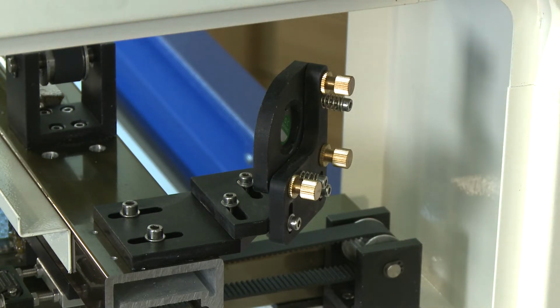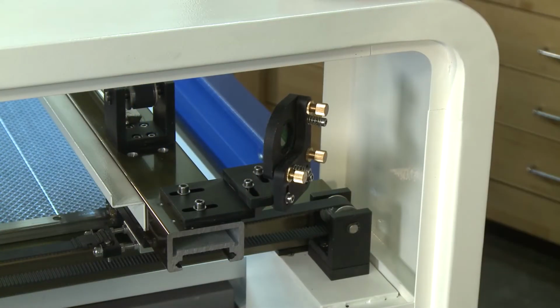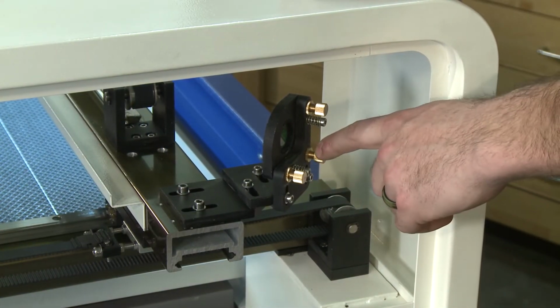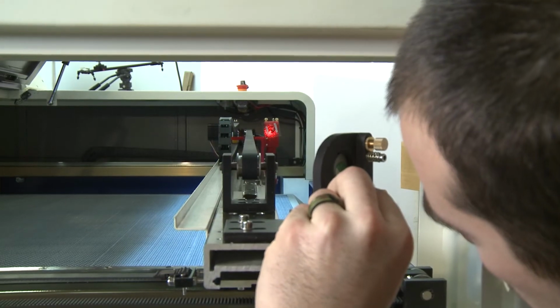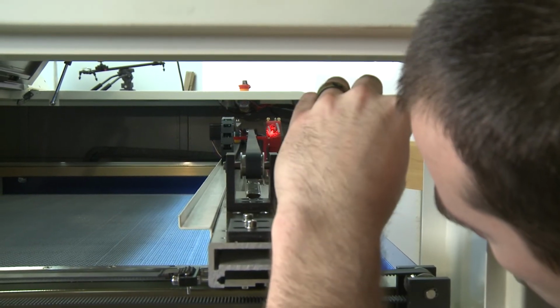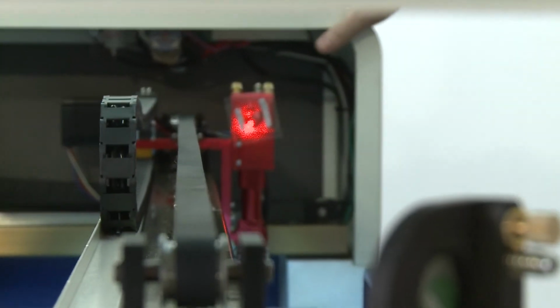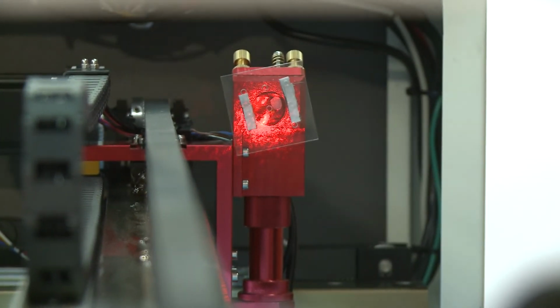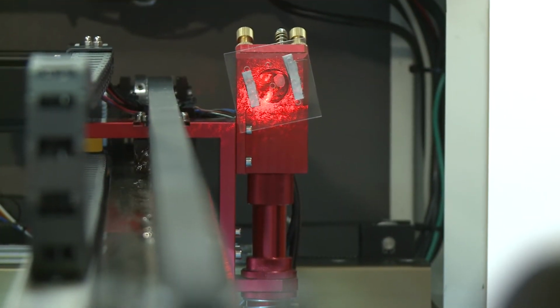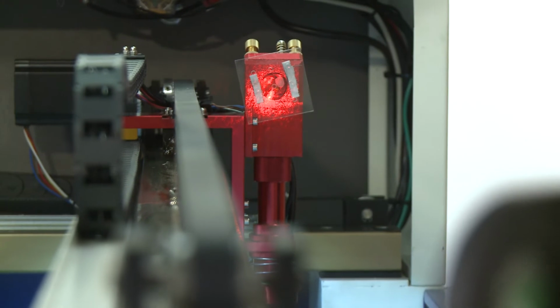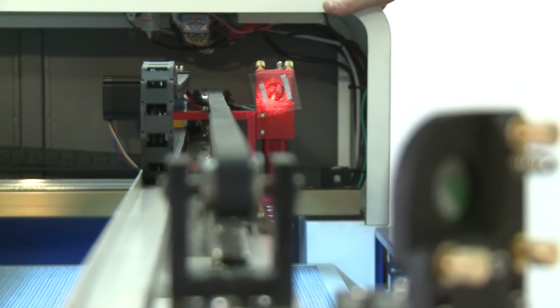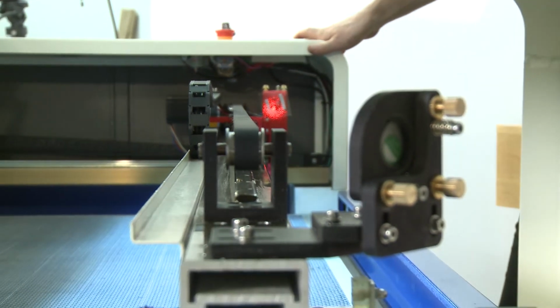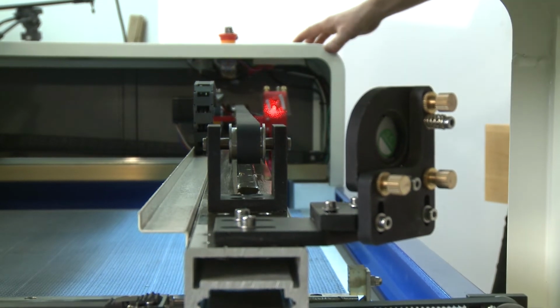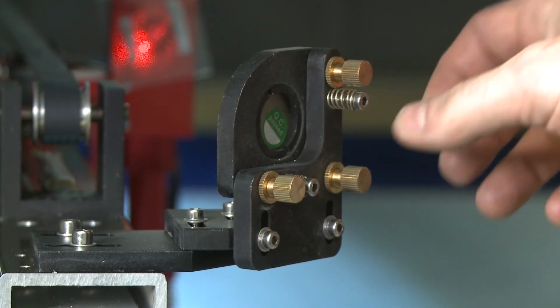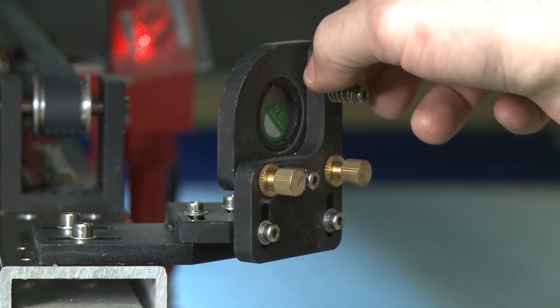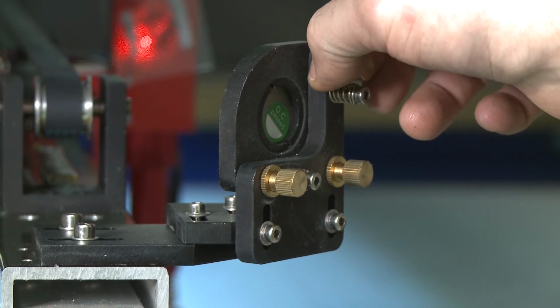To begin the trial and error fine-tune process, use the brass knobs to move the alignment laser, or the reference laser, approximately the amount that you need to move to get the actual laser on center. Once you've adjusted the mirror to approximately align the real laser beam where you think it should end up, repulse the laser and double check your work. Once your laser beam is on center and satisfactory, simply use the lock nuts to lock everything down in place.